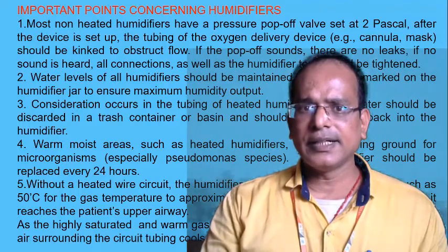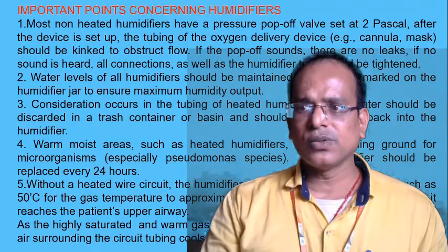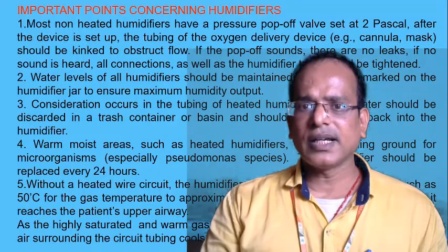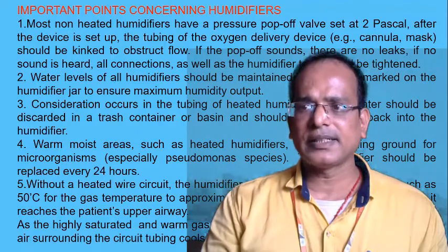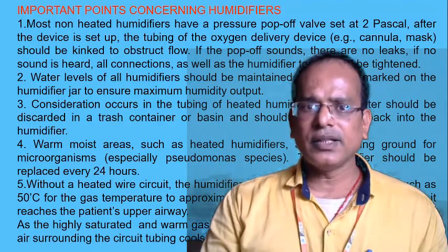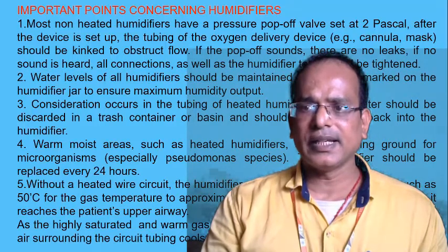If the pop-off sounds, there are no leaks. If no sound is heard, all connections as well as the humidifier top should be tightened. Second one, the water level of the humidifier should be maintained at the level marked on the humidifier jar to ensure the maximum humidity output.